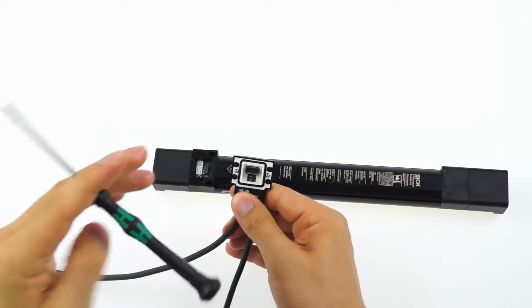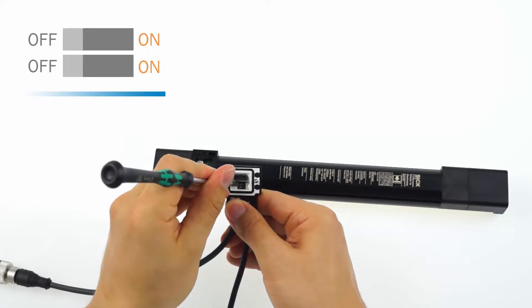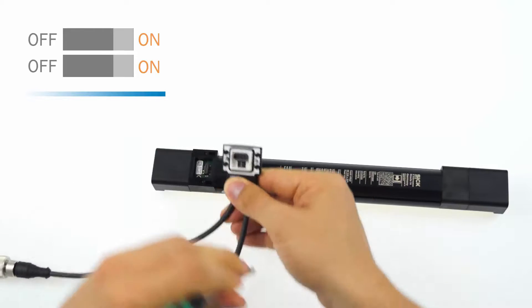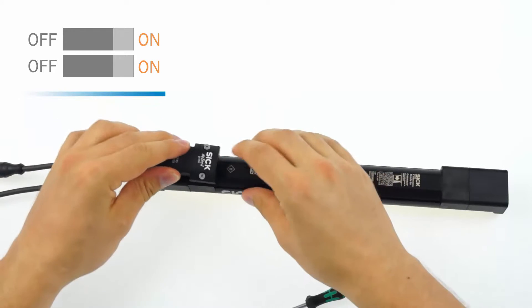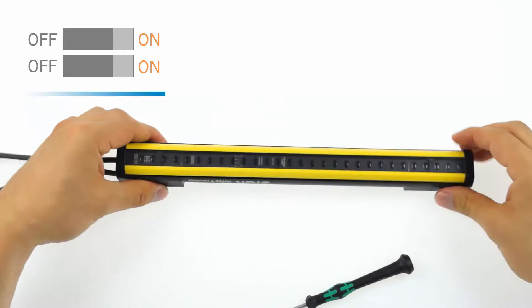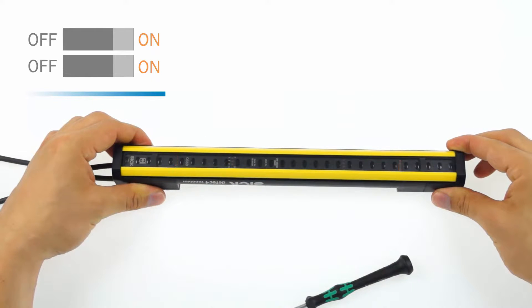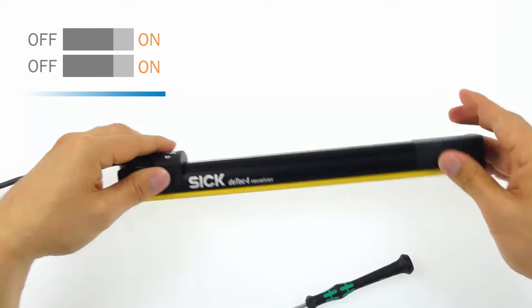In the first step, detach the system plug. Set both of the dip switches to on and put the plug back on the device. Switch on the power. The field LEDs are flashing green and yellow now. Disconnect the device from the power supply within 10 seconds.